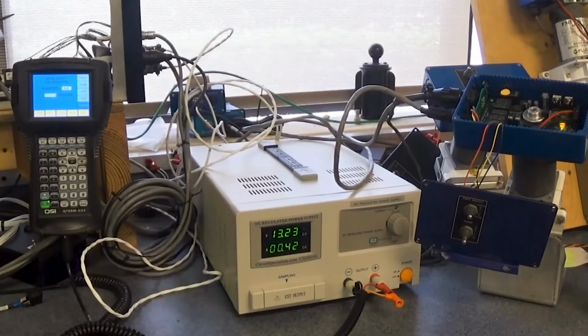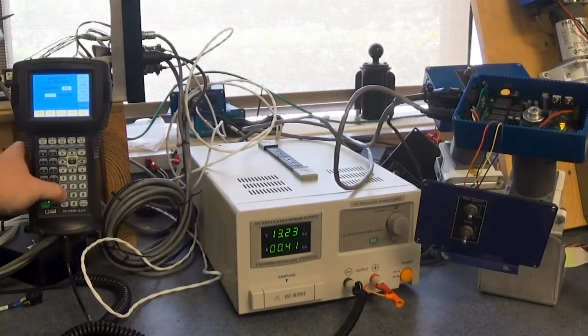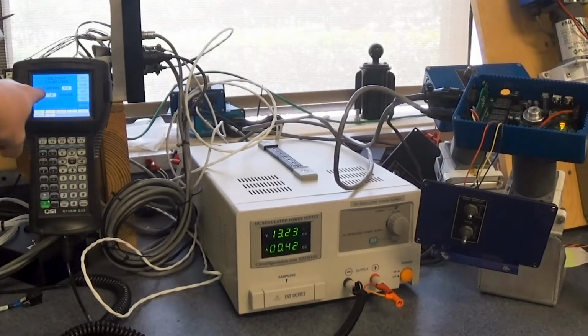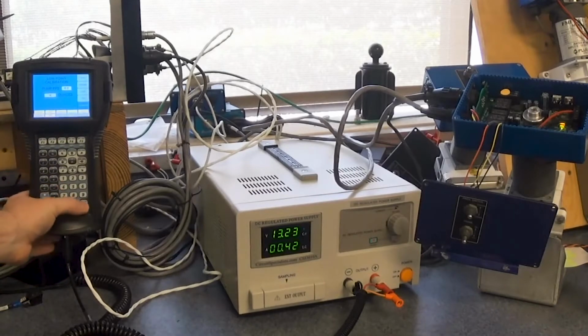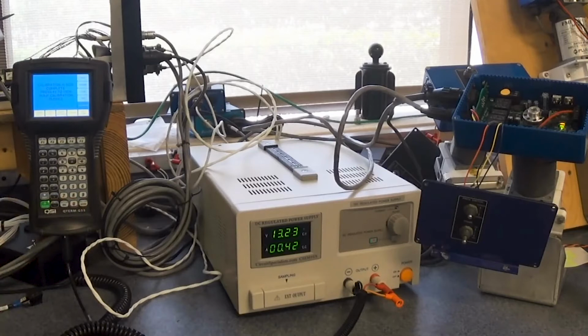So even though there is a flow going through here, and we can measure it, we'll just say, for example, that we got 16 ounces for our high, and we'll put in 7.9 for our mid, again, checking that the pulses per second are again still 0. And our low pulses per second is also 0.0. We'll put in a value of 4 just for a demonstration. Notice that we actually have a calibration slope that looks normal in this scenario as well.